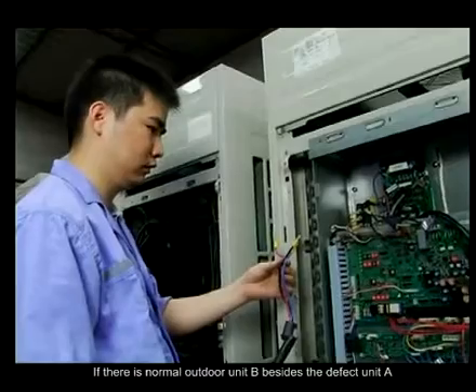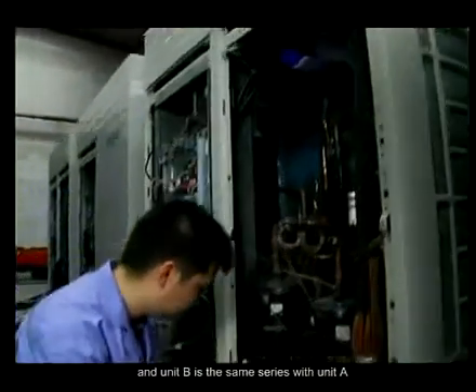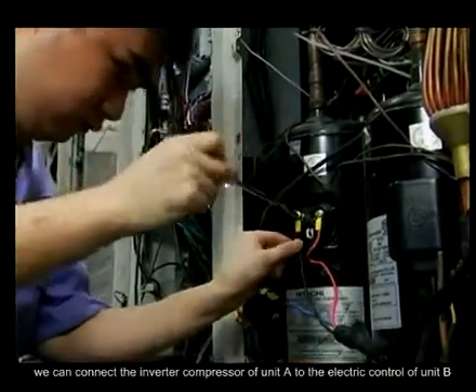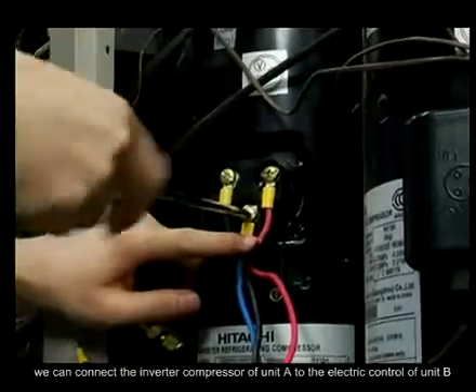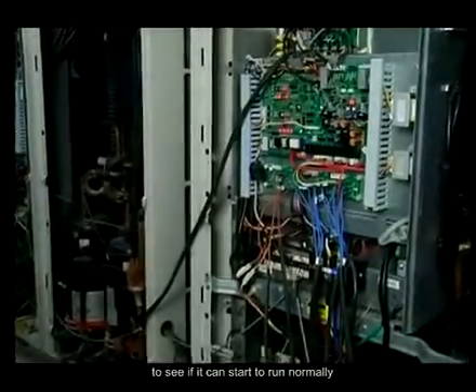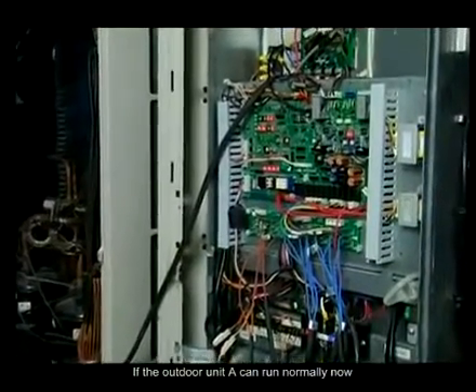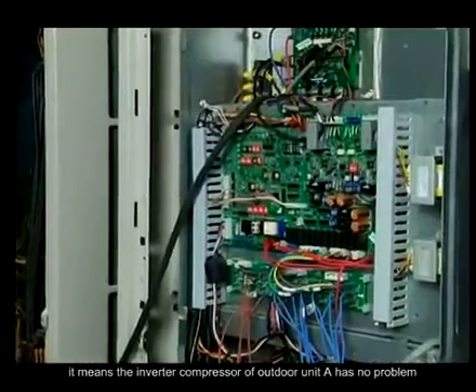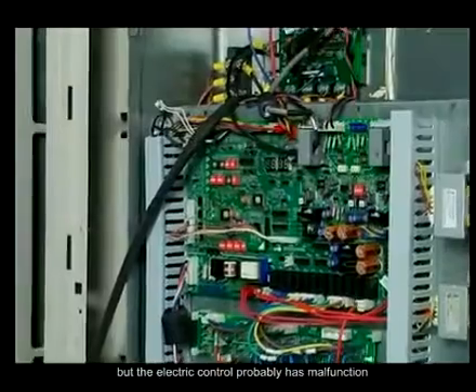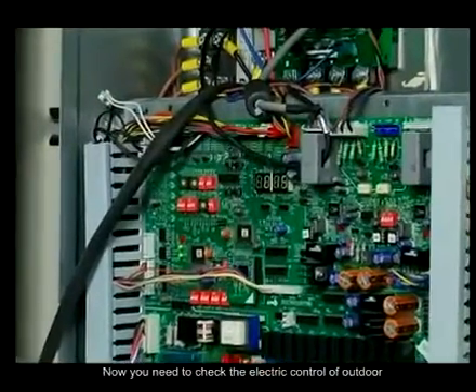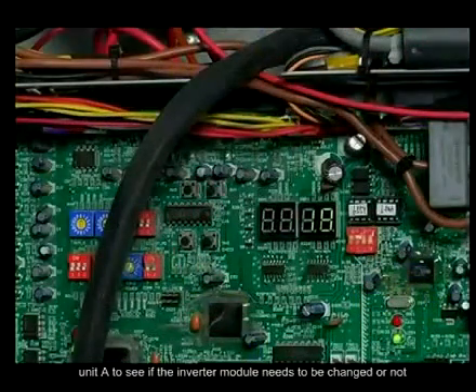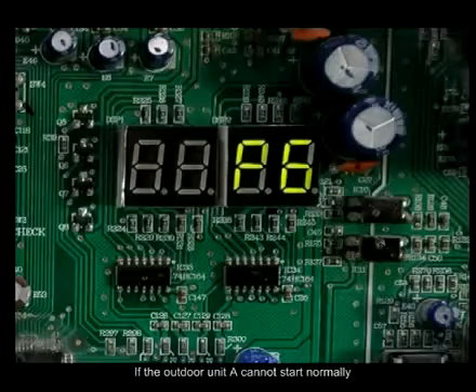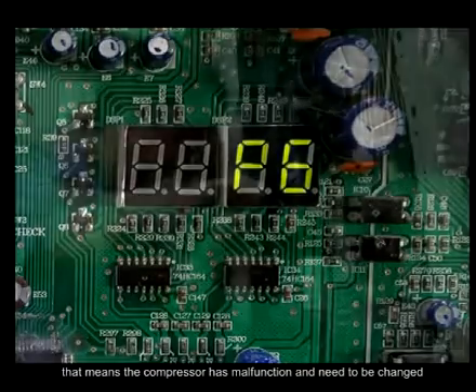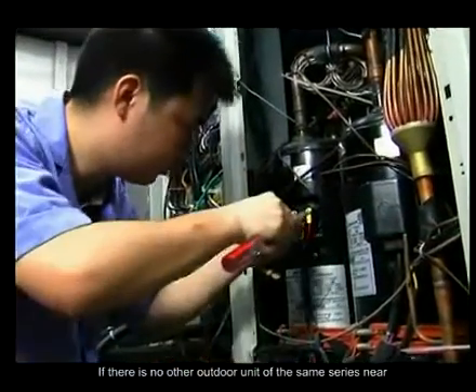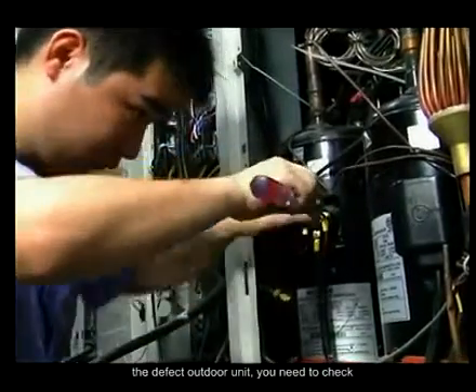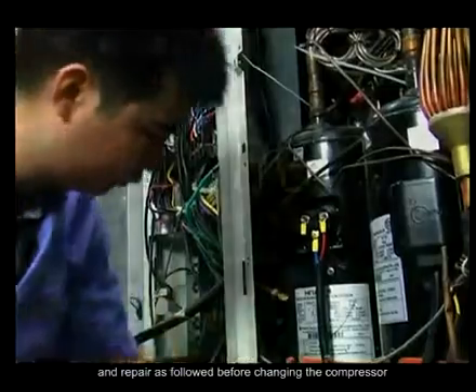If there is a normal outdoor Unit B besides the defective Unit A, and Unit B is the same series as Unit A, we can connect the inverter compressor of Unit A to the electronic control of Unit B to see if it can start to run normally. If outdoor Unit A can run normally now, it means the inverter compressor of outdoor Unit A has no problem, but the electronic control probably has a malfunction. Now, you need to check the electronic control of outdoor Unit A to see if the inverter module needs to be changed or not. If outdoor Unit A cannot start normally, that means the compressor has a malfunction and needs to be changed. If there is no other outdoor unit of the same series near the defective outdoor unit, you need to check and repair as follows before changing the compressor.